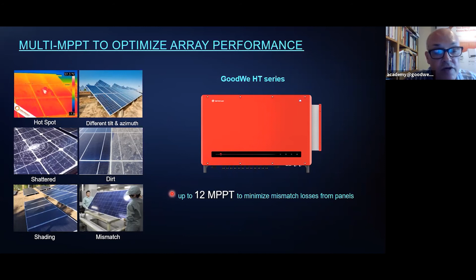So what we're saying here is that the performance of the system is only as good as the panels and the number of trackers that you have within your system. So for instance, if you have a problem that's developed on a panel or on a particular string, I don't know, a hotspot, or it's a very dirty panel, or it's broken, something like that, then you're only going to affect one string. You may reduce the performance of one string. Now, one string out of 12, you can see the benefit here of having an inverter that's got a high number of trackers, particularly, of course, if you scale that up where you've got a number of inverters within your system, then you're only affecting one string out of many, many strings.